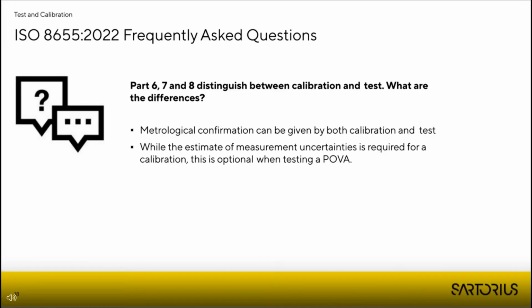And a second important question: the new ISO distinguishes between calibration and test. What are the differences? A metrological confirmation can be given by both calibration and test. The only difference is that the measurement uncertainty must be given on a calibration certificate, while this is optional when doing a test. So on a test report, the measurement uncertainty is not required, while this is a must on a calibration certificate.